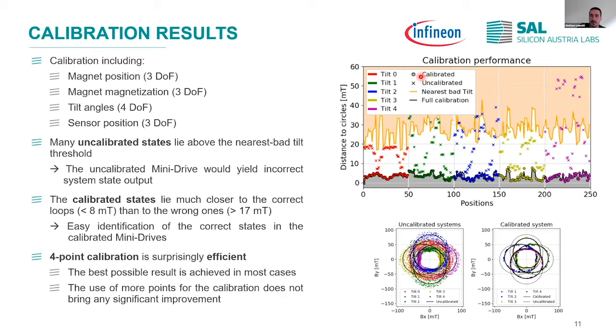When we take instead the calibrated states, shown as circles at the bottom of the plot, we are much more precise, and we are much closer to the correct magnetic loops that identify the correct state of the system instead of the wrong magnetic loops. So the calibration is needed for proper operation of the mini drives, and this plot also shows that using just 4 points for each magnetic field cycle is sufficient to achieve a very good result. If we compare with the calibration done with many more points, 250, shown by the red line that is partially covered by the colored dots, we can see that the result is almost the same. So the 4-point calibration is very efficient, very easy for the user to implement, and gives a very good result for the final calibration of the device.